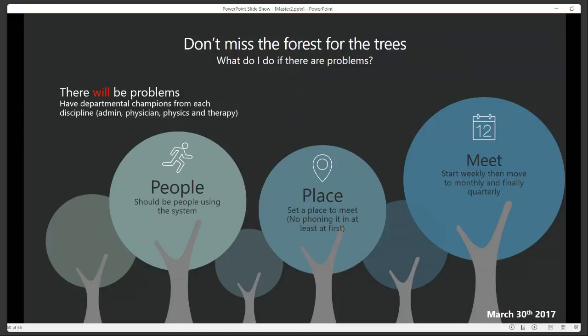You're going to have problems rolling it out because everything you thought of in commissioning may not be what the therapist thought of when they rolled it out in the clinic and started using it. So you need to have people from all steps of the process that are using the system agree to take part in meetings at a set place. I always recommend no phoning it in, at least at first, which is usually the most difficult for the physicists and the doctors, and then meet starting weekly.